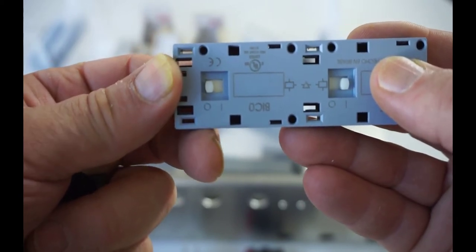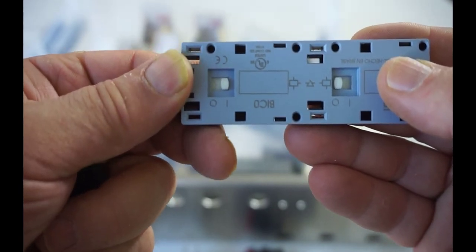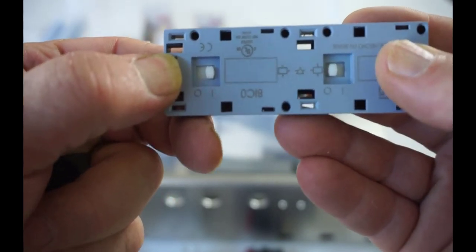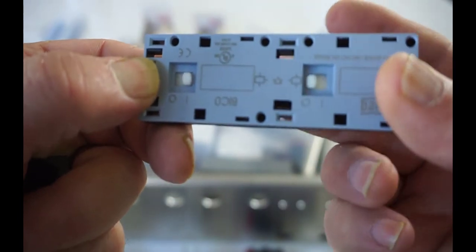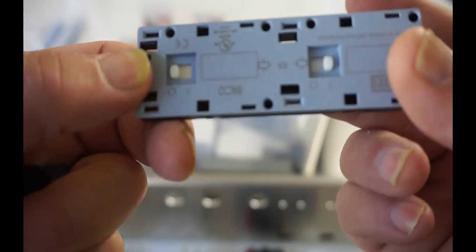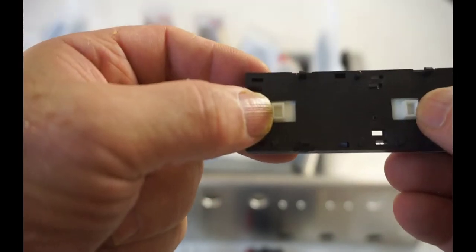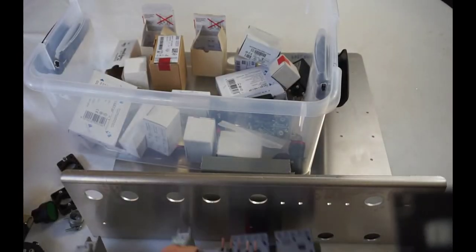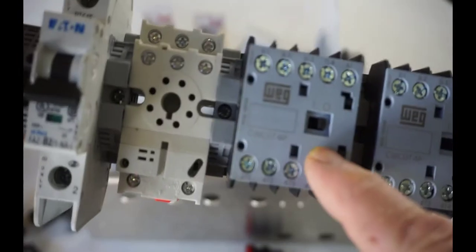If I have them both off, this will work and then this will work. But if this one is turned on, it'll prevent the other one from being turned on. If it turns off, then the one on the left turns on, this cannot operate. I'm pulling on it and nothing will happen. Go back, turn the left one off, and now I can turn the right one on and off all I want. You can see that these little tabs here, they mate with the little tabs here on your contactors.